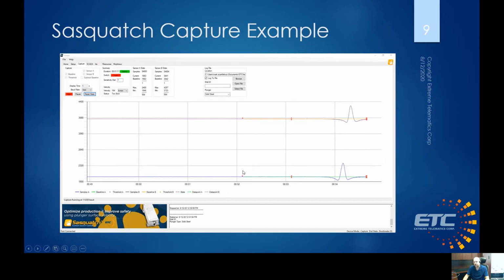All right, so here's a capture of the Sasquatch. So it looks very much like the Cyclops. You have your baseline. There's two different baselines here. There's two different sets of real samples. There's obviously two sensors on the Sasquatch, as well as the threshold is set here based on the switch setting. We've got this up to sensitivity dial 7, so that's a really small change we're looking at. And you can see we deviate from the baseline, and we're pushing and pulling that magnetic signal, which gets triggered as an arrival.